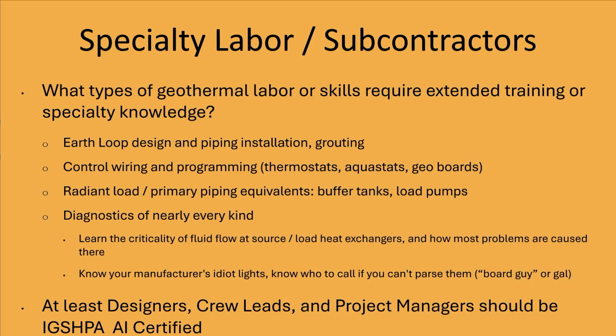Control wiring and programming for thermostats, aquastats, and the geothermal board set is typically a specialty. If you just have a forced air geothermal system with one thermostat, you can probably get away with someone who knows how to wire an air source heat pump without extra training. Otherwise these things are specific and need to be done right, since the programming for geothermal is quite different from air source heat pumps in the stats and other places.